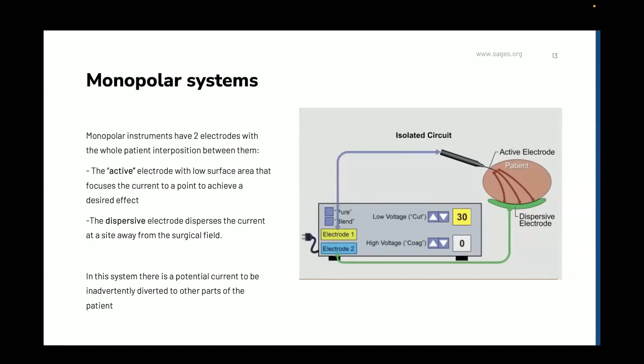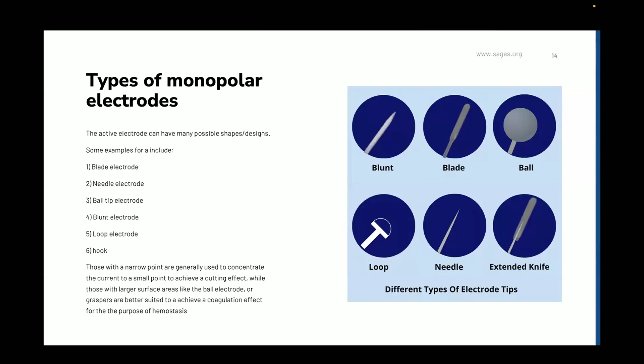Versus, there are different types of tips that could be used on a monopolar electrode, and essentially the smaller the tip, such as in a blunt or in a needle tip, the higher the current is going to be focused on a small surface area, leading to higher temperatures on that tissue, versus using a ball which distributes more of the current across a higher surface area, leading to more coagulation, less cutting, which is usually used for fulguration and leads to better hemostasis.